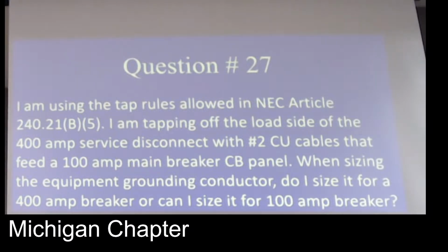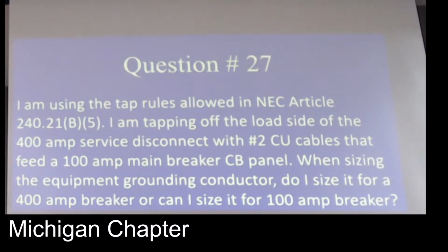And this is a good question, because you've got two different devices, and you need to know which one to use. So where I go with this is 250.122, and specifically Table 250.122. If you read the heading on the left-hand side of the column, it says rating or setting of the overcurrent protective device ahead of the conductor. So this is going to be an interactive question. I've got a 400 amp overcurrent device and I've got a 100 amp overcurrent device. Which device is ahead of my conductor? 400. I heard somebody say it. If I had a candy bar, I'd throw it your way. So yeah, that's the answer.